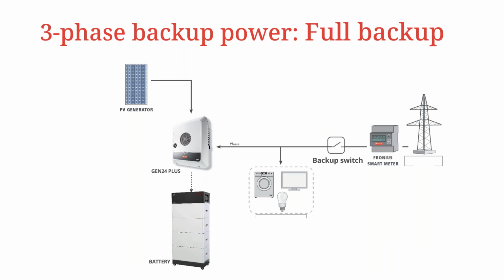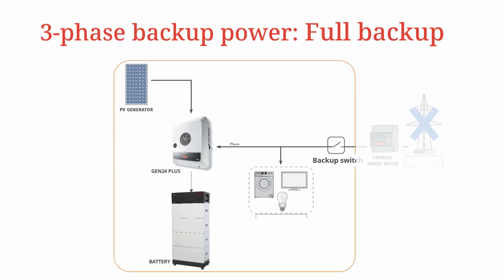So this is just an example of 3-phase backup power with a full backup. If you've lost the grid, for example, the grid has failed, you're then relying entirely on your Gen 24 and your BYD battery storage. Your backup switch is then opened. This will allow your PV generation to recharge your battery, as well as supply your loads that are being demanded, while also using the battery to help feed those additional loads.